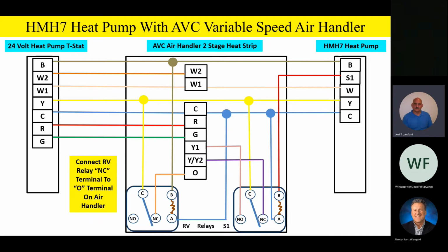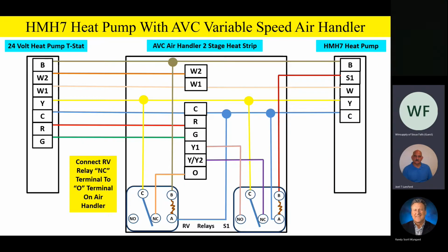Now, when we go into the heating mode of operation and we energize B, what's going to happen, we're going to break that O terminal, and we're going to tell the air handler, or the variable speed indoor furnace if it's a furnace, hey, we're not in the cooling mode anymore because we broke the O terminal. So please remember, on a variable speed product, we need that O terminal energized in the cooling mode for advanced functions. Any questions or comments on how this is wired so far? No, I think we're good, Joel.